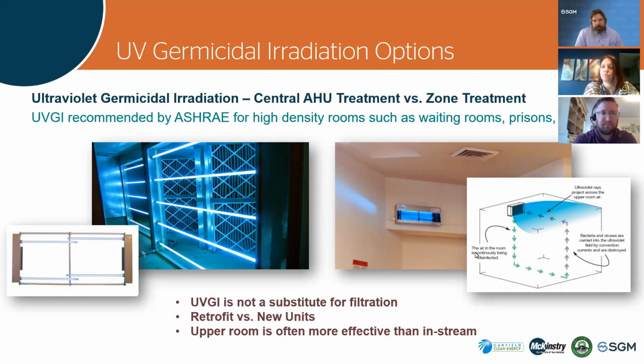But also, you can't just say UV is going to fix it all. It has to still be accompanied by filtration. So on these particular units that we've been seeing shipped out brand new with UV, there's a MERV 8 pre-filter, the UV, and then a MERV 14 final filter. And that is for hospitals. One of the few areas in hospitals that are going in this direction. It's my understanding too that the overall energy impact of implementing UV is generally pretty minimal, right? Yeah. Of course, you have the higher filtration rate, so you have to adjust the fans to recover that pressure drop.